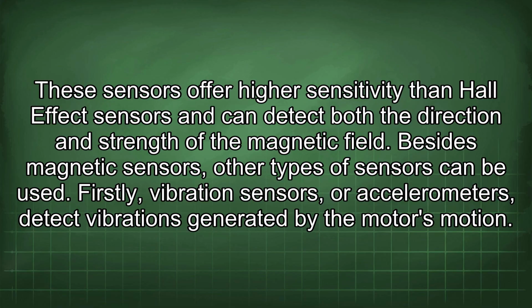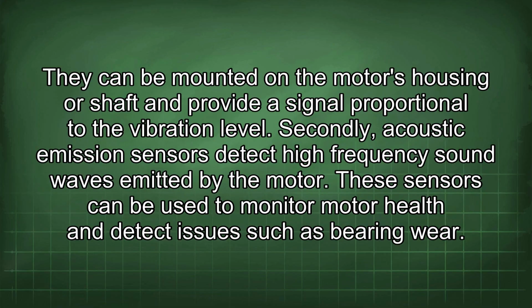Firstly, vibration sensors, or accelerometers, detect vibrations generated by the motor's motion. They can be mounted on the motor's housing or shaft and provide a signal proportional to the vibration level. Secondly, acoustic emission sensors detect high-frequency sound waves emitted by the motor. These sensors can be used to monitor motor health and detect issues such as bearing wear.